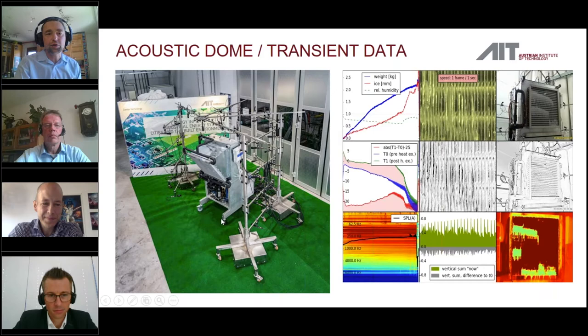Then you can capture all the transient data. This means you are not only calculating a sound power level at one special situation—you go for a measurement on the whole operating range, on whole operating points, and you also see frosting and defrosting effects, which you can see here on the right side.